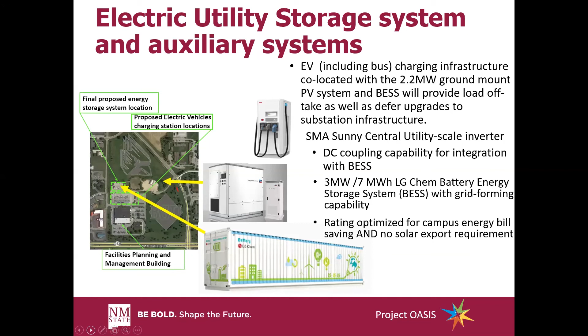also has an additional capability with battery systems: compatibility with battery systems. It has an additional DC input to allow PV plus storage systems to be DC coupled. This is a valuable feature as it can increase overall system efficiency by eliminating two DC-AC and AC-DC conversions. Further, we envision that an EV, including bus, charging infrastructure, co-located with the 2.2 megawatt ground mounted PV system and BESS will provide load offtakes as well as defer upgrades to substation infrastructure. A multi-vehicle charging station, such as an ABB Terra shown here, could be a beneficial feature for electrification of the campus.